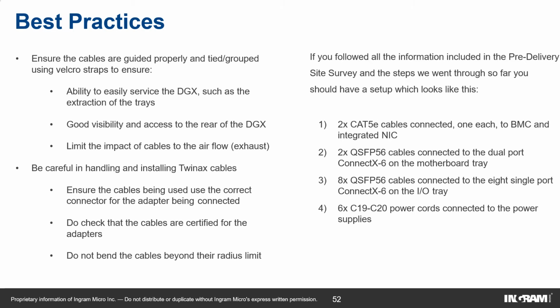Here are some best practices: ensure the cables are guided properly and tied or grouped using a Velcro strap to maintain the ability to easily service a DGX, such as removing or extracting a tray, good visibility and access to the rear of the DGX, and limit the impact of the cables on airflow or exhaust. Be careful in handling and installing the Twinax cables, ensure the correct connectors are used for the adapters being connected, check that the cables are certified for the adapter, and make sure you do not bend these cables beyond the radius limits.